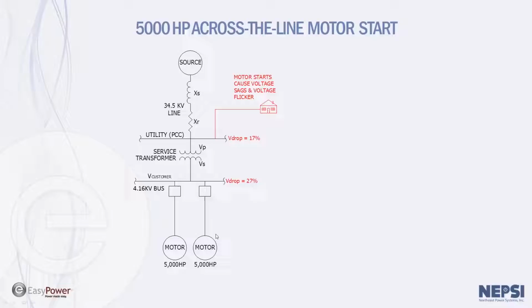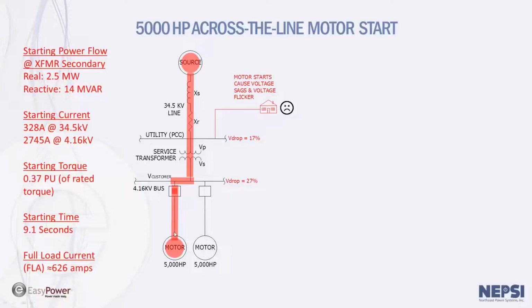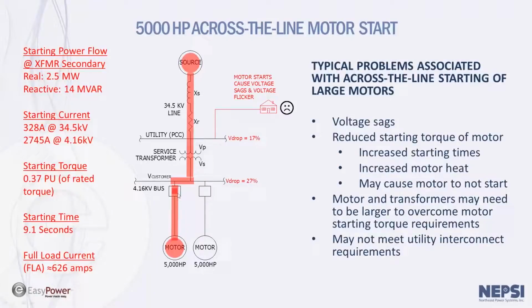Pictured here is a 5,000 horsepower motor connected to a 5 kV bus, and this is an across the line motor start application. This is just to review what happens during a motor start. When a motor start occurs, the 5 kV breaker to the motor is closed. It results in a draw of reactive power through the system. In this case, the reactive power flow was 14 megavars. It's often the case that the reactive power requirements of a motor can be up to 4 to 6 times the nameplate rating of the motor.